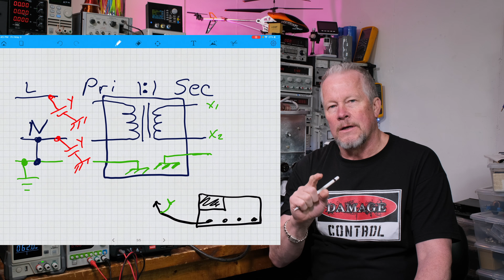And so if your chassis is floating, like I've been in labs where on an oscilloscope, they use those cheater plugs, the 3 prongs to 2, so they don't have any potential issue blowing up their scope. They have to be careful, because now the 2 chassis connections, the chassis is floating. But now you have 2 capacitors in series from line to neutral, and the center point is chassis. So it's a voltage divider. If you had 120 volts, you'd basically have 60 volts at your chassis. So now your chassis is floating around at 60 volts. You just have to be aware of that.